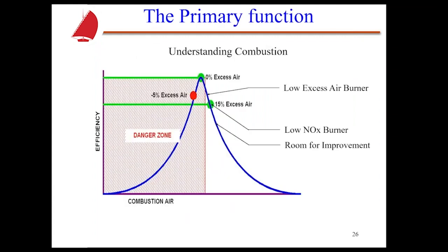Now, the primary reason we actually buy these controls and use these controls is because we want to make sure that across the combustion rate or firing rate range, from low fire to high fire, we would love to have that burner at the optimum point where we have zero excess air in that combustion. Now, no one does that. We always dial in some excess air. There's no question. A lot of burners like that also. But if we can have that perfect point across the firing rate range and actually record that, which is what we will be doing when we commission it, then as it modulates, it's going to make sure that the air and the fuel is dialed in exactly where it needed to be. And that's the primary function of the control.